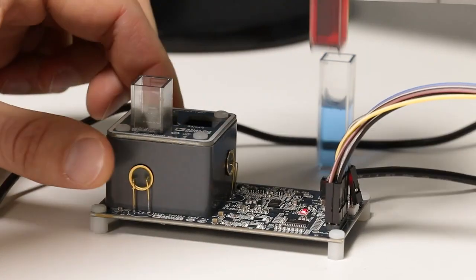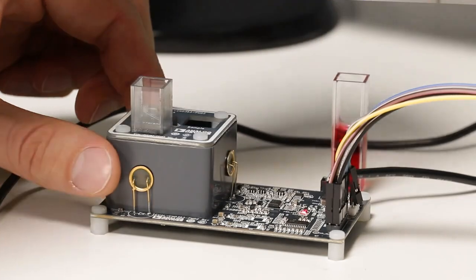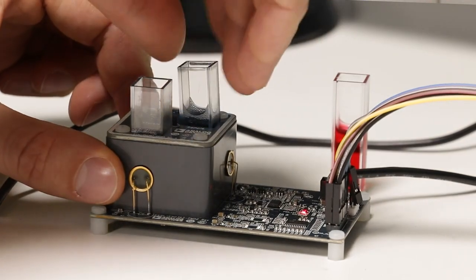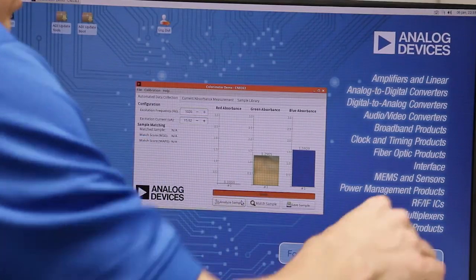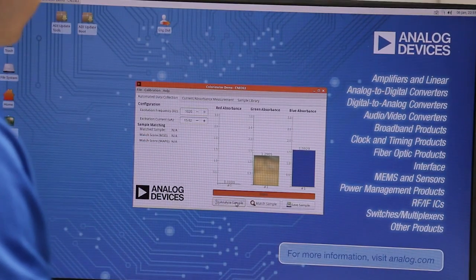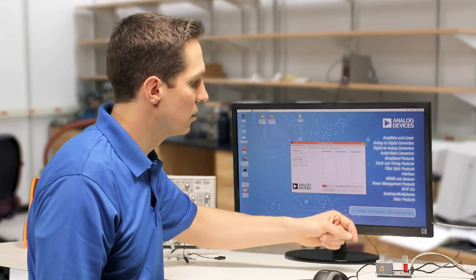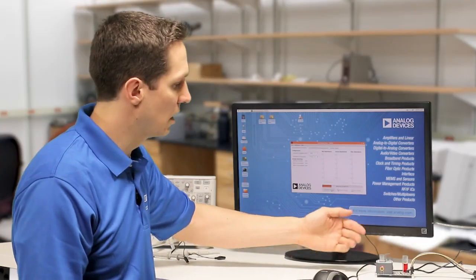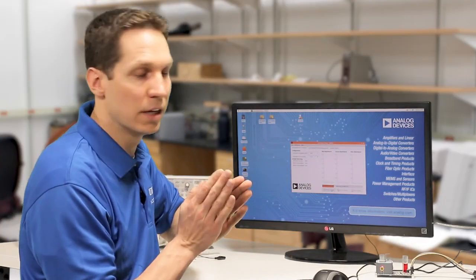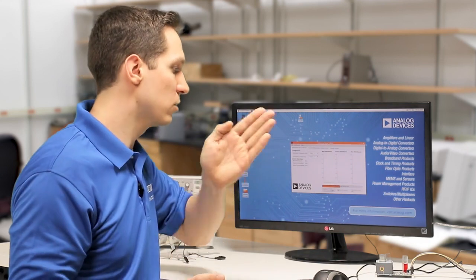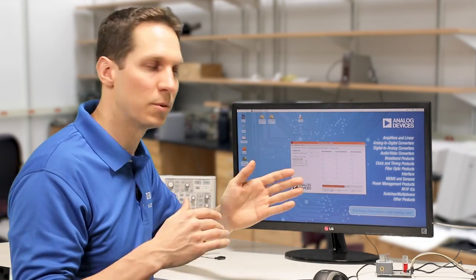So we can take this out and transfer a red sample, switch it out for a blue sample and run it again. And again what it's doing is it is lighting up these lights, putting it through a beam splitter, running the light through distilled water and also through the sample and then comparing the absorbance.